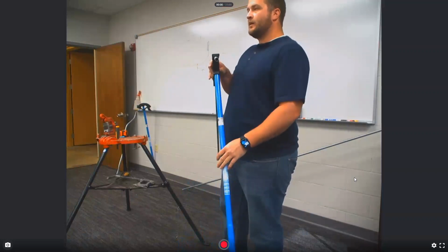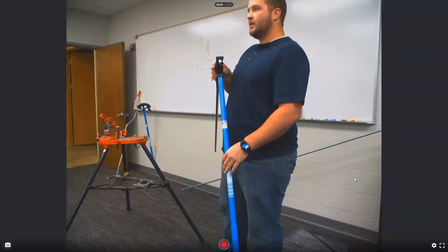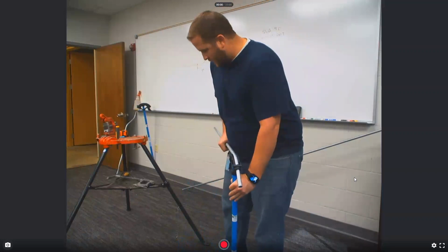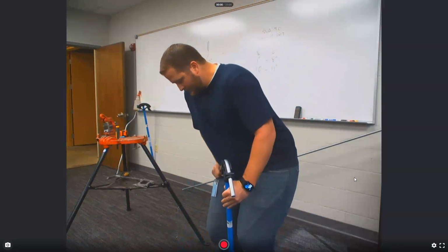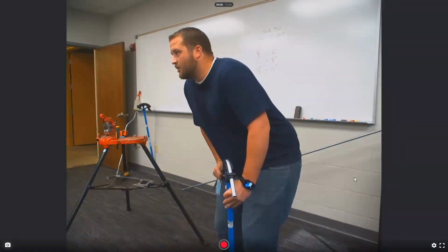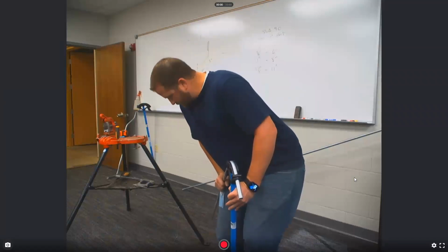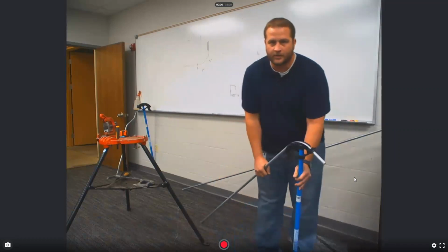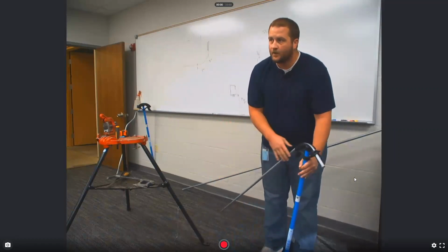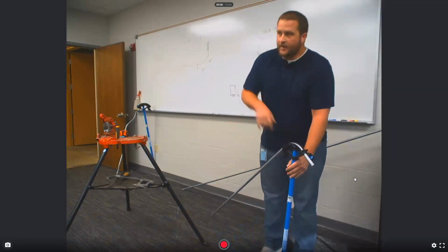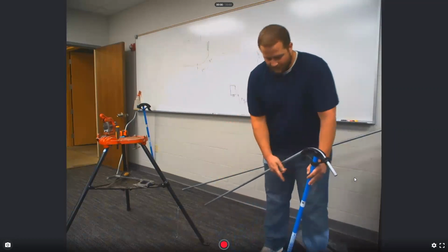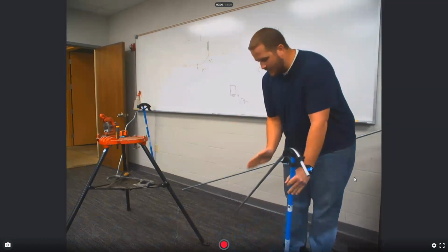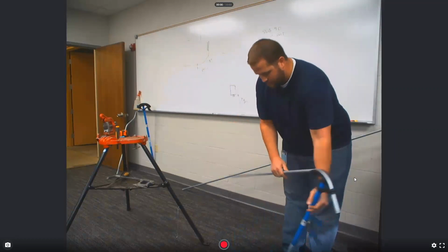What's the matter with making the whole bend with the end of your bender on the ground? Seems like you have a lot more leverage. Actually, we do have more leverage with it on the ground, but you're just not quite going to make it. You can do it, but eventually you fight it. What you find when you're making bends in the lab, where all of the bends are made in the air, is that the bottom of the bender is going to start to slide out from underneath you. If you're trying to make that huge bend, eventually it's going to start sliding around.